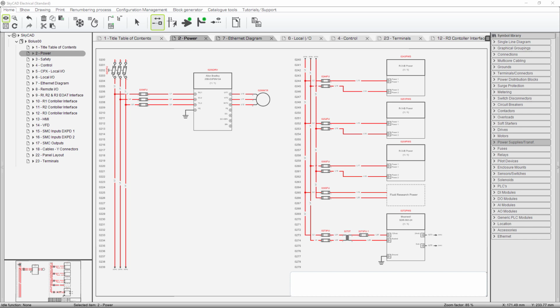I prefer flange mount, but they're more expensive. The advantage of a flange mount is they're easier to operate than wrestling with those through the door disconnects. Either one works. All it does is interrupt power from outside the panel with the door closed. And they all have some sort of thermal circuit interrupters, whether it's a circuit breaker or fuses. I'm using a fused disconnect, and it's probably a 30 amp rating, 300 volt 30 amp. They're rated by voltage and by current.